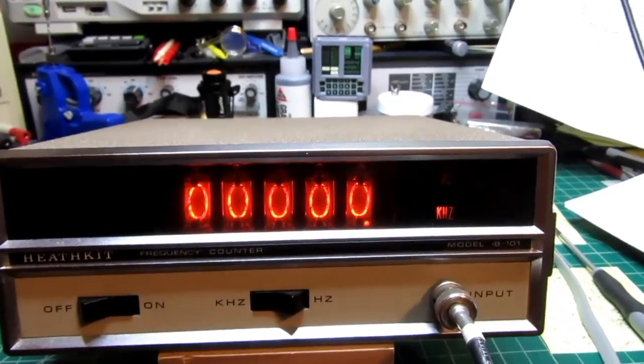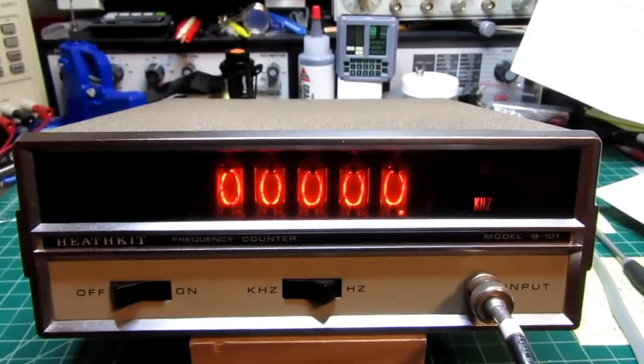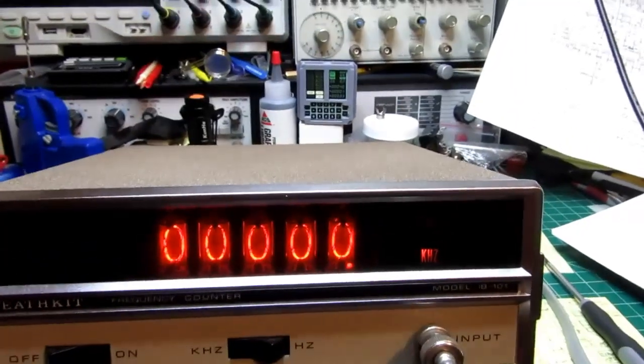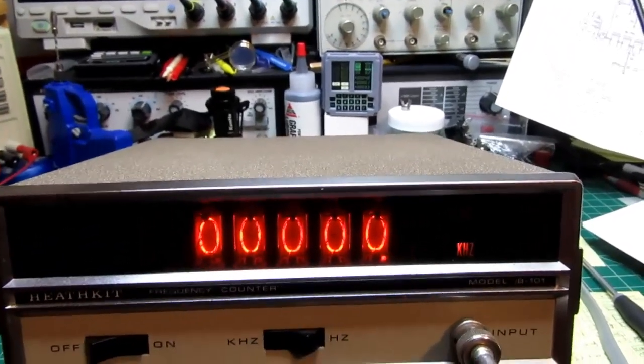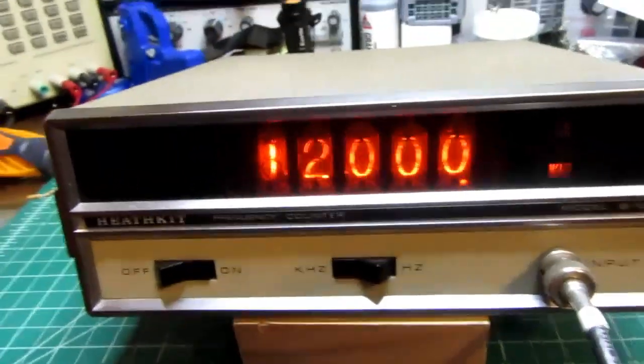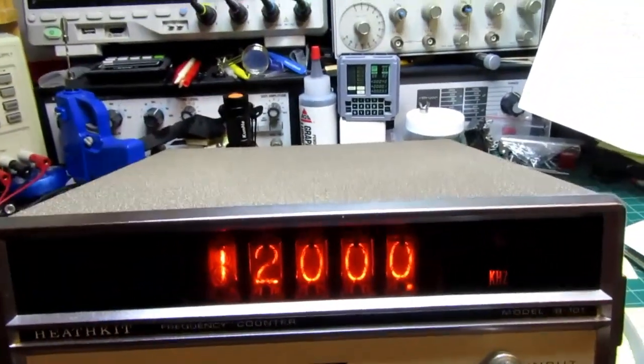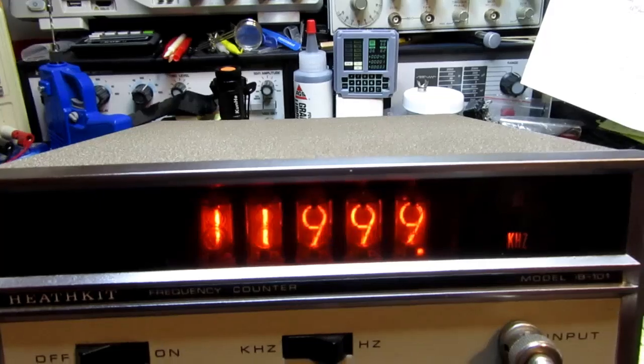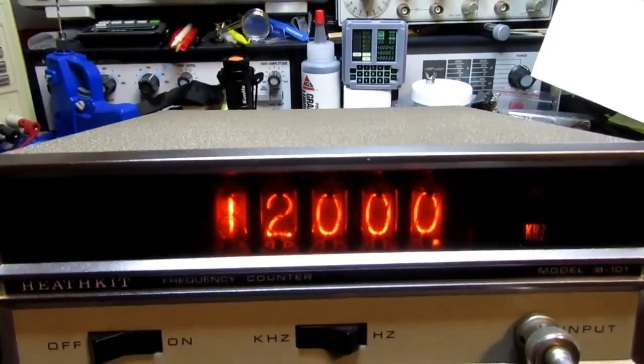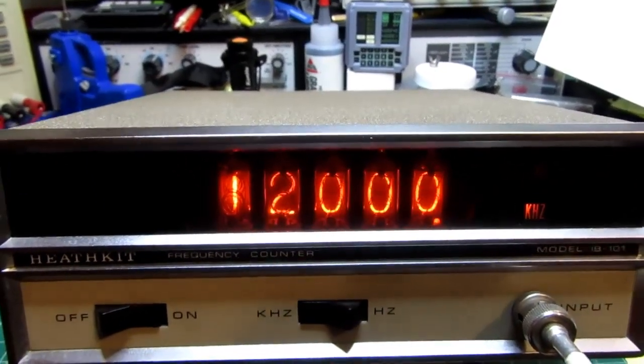And it's kind of bonking here. It doesn't like the higher frequency. It's supposed to go to 15 megahertz. So that was just the sensitivity being a little off. I just tweaked it slightly, and now it's giving me the 12 megahertz. It's right on the point of rolling over, so that's why it flickers.